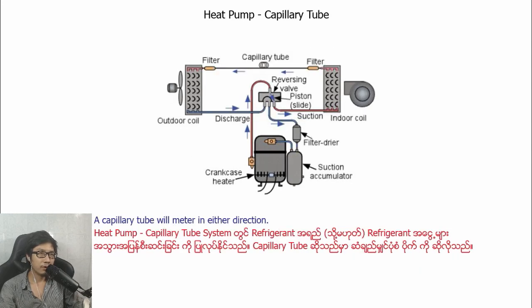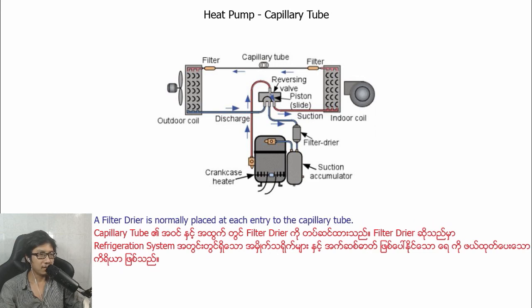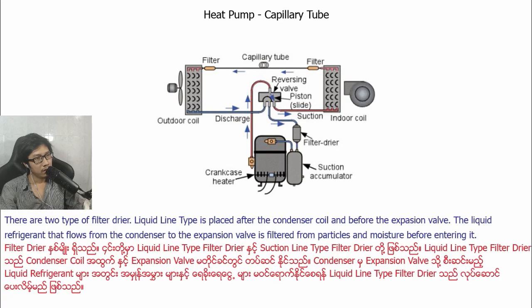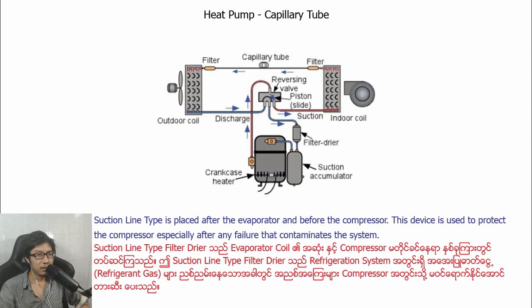Heat pump capillary tube. A capillary tube will meter in either direction. A filter dryer is normally placed at each entry to the capillary tube. There are two types of filter dryer. Liquid line type is placed after the condenser coil and before the expansion valve. The liquid refrigerant that flows from the condenser to the expansion valve is filtered from particles and moisture before entering it. Suction line type is placed after the evaporator and before the compressor.